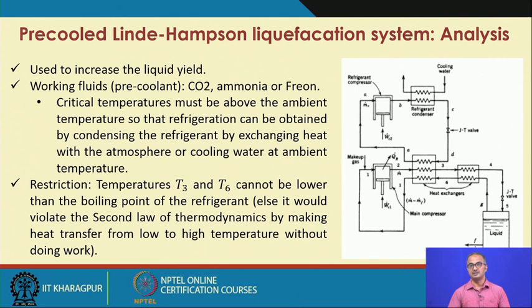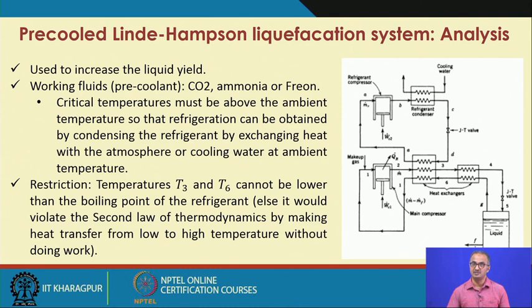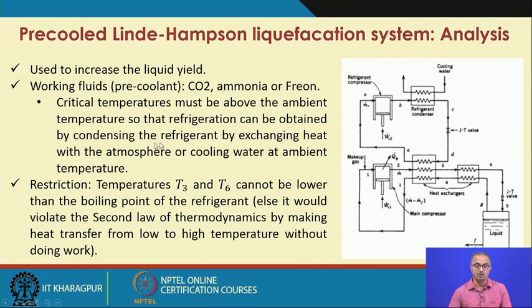Now we go to the pre-cooled Linde-Hampson liquefaction. The basic system remains the same as for the pre-cooled refrigeration. We need it because we want to increase the liquid yield — in liquefaction we are concerned about the yield, whereas in refrigeration we are concerned about the cooling. The working fluids or pre-coolants here can be something like carbon dioxide, ammonia, or some freon. The critical temperatures of the pre-coolant must be above the ambient temperature; otherwise we will not be able to get the phase change.